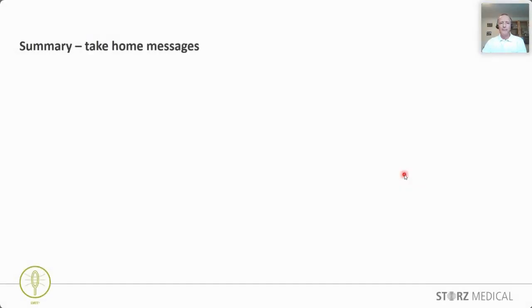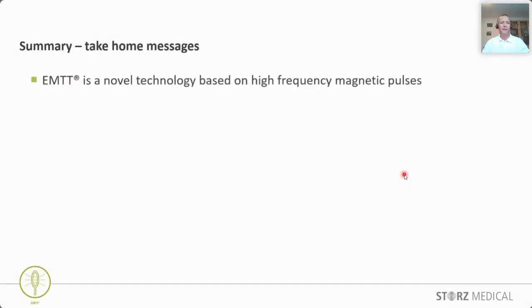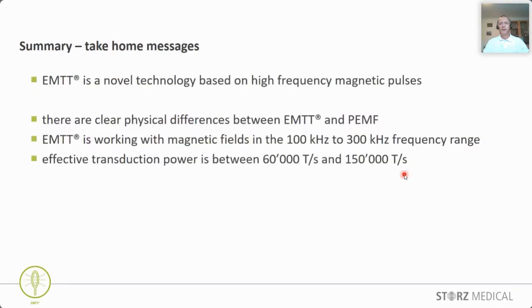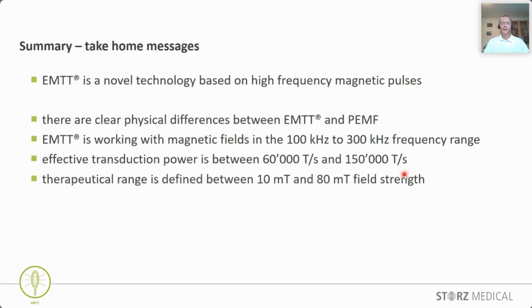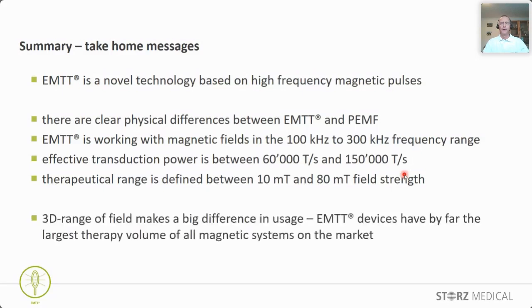So I'm back to the summary of the take-home messages. The EMTT, this effective transduction power, is between 60,000 tesla per second and 150,000 tesla per second. The therapeutic range is defined between 10 millitesla and 80 millitesla field strength. And as you've seen from the simulations, the 3D range of the fields makes a big difference in usage — the EMTT devices have by far the largest therapy volume of all magnetic systems on the market.